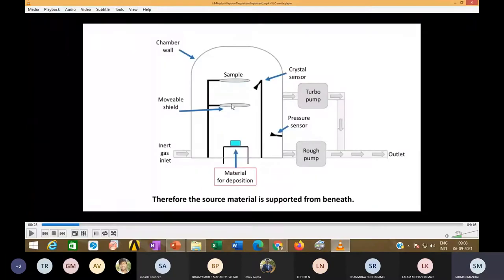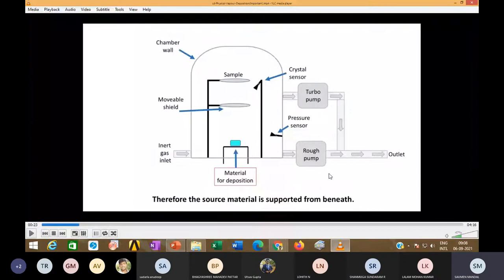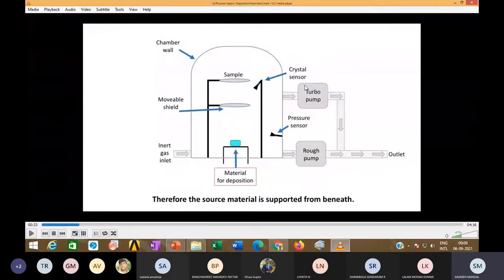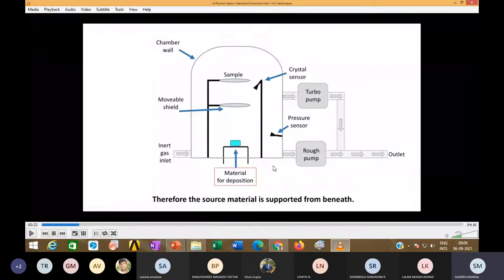After fixing and closing the shutter and chamber, the vacuum process starts. First, you start with a roughing pump, which can reach around 10^-3 millibar. Only after achieving that vacuum should the high-end pump — like a diffusion pump or turbo molecular pump — start. The roughing pump is then no longer required, and the high-end pump will take you down to 10^-6 to 10^-7 millibar for deposition.